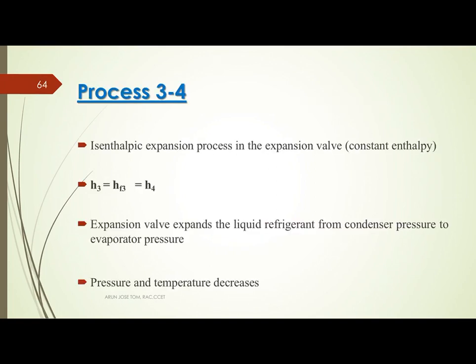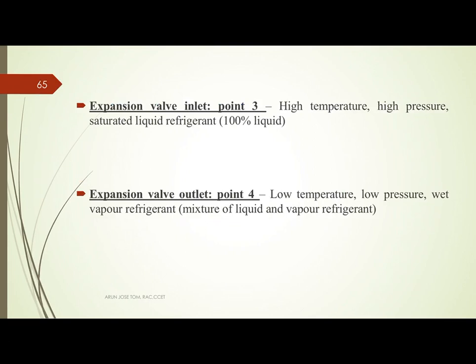The next process is process 3 to 4 — isenthalpic expansion. During this process, the enthalpy of the refrigerant remains constant, so H3 equals H4, and H3 equals HF3 equals H4. The expansion valve expands the liquid refrigerant from condenser pressure to evaporator pressure. Pressure and temperature decrease due to expansion. The exit of the expansion valve is low temperature, low pressure wet vapor — a mixture of liquid and vapor refrigerant.